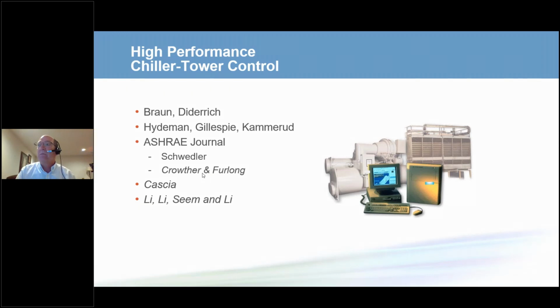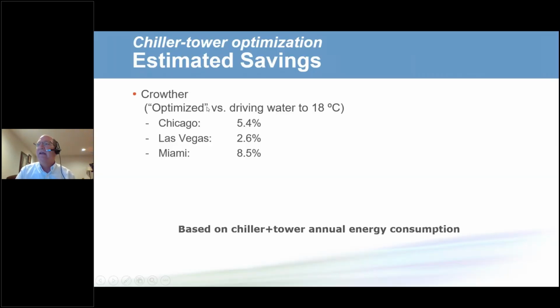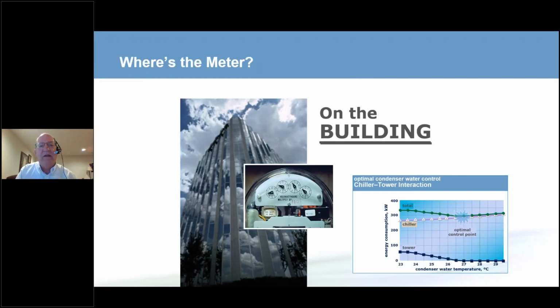In addition, Hugh Crowther in his article looked at different operating temperatures in different locations. And as we get to more humid climates like India, the savings available between trying to make the coldest tower water temperature possible and finding optimized can be, and I've seen, between 8 and 15% savings of your chiller plus tower energy usage just by finding that optimal set point. What we have to remember again, however, is the building owner pays for the entire system. The meter is on the building. It's the chiller plus the tower energy consumption. The chiller power and energy goes up, but that's not what matters. What matters is the system energy consumption.